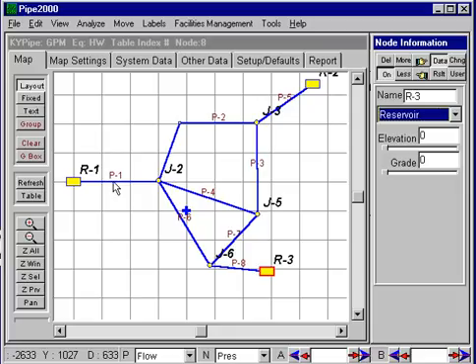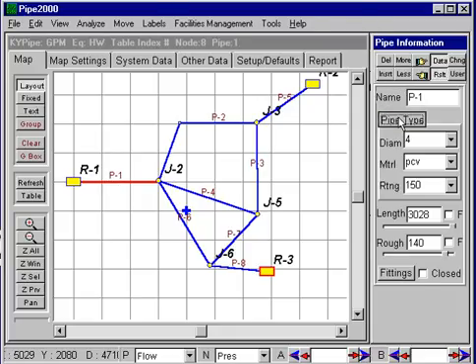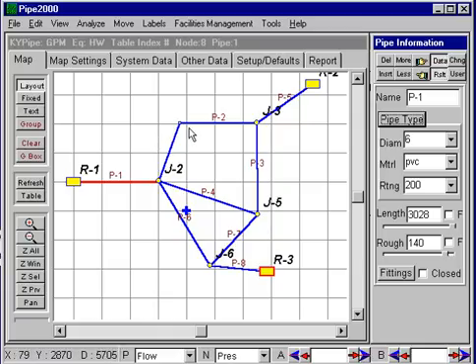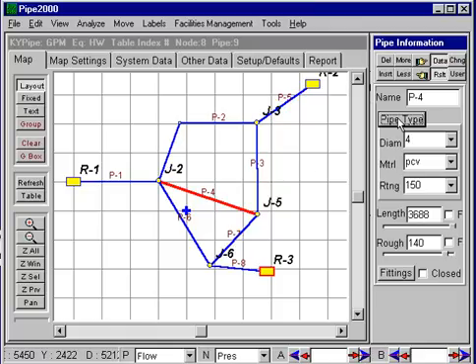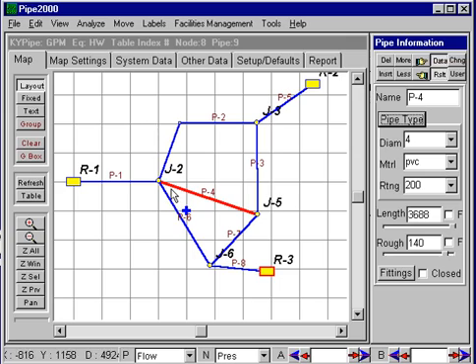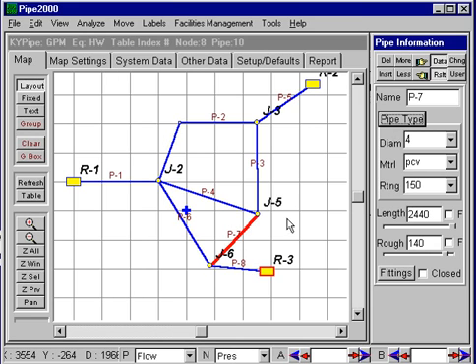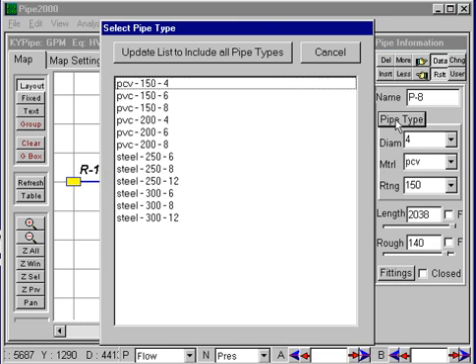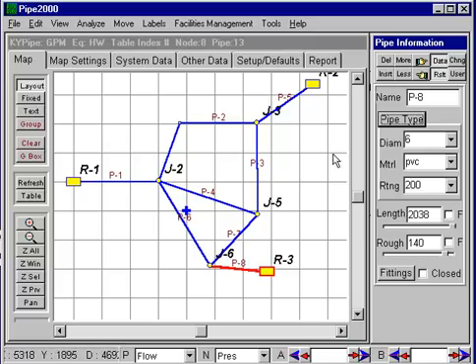Now I'm going to enter pipe data. We've already got some pipe types in there. I'll select the pipe and make this a six-inch PVC. I'll make this one a four-inch PVC, and the remaining pipes six-inch PVC. Note that as we enter that, we get the length scaled and the roughness is entered from the pipe type data. So basically all the pipe data has been entered except minor losses, and we won't include any of those.